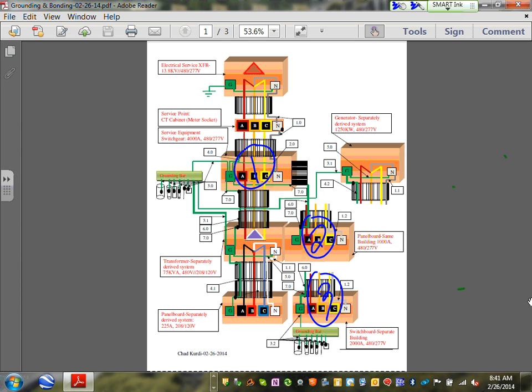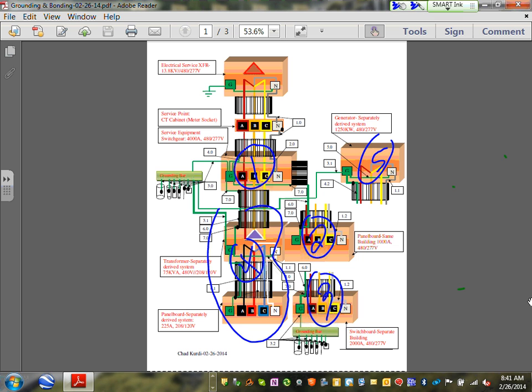And I need to do number 4. Number 4, guys, is grounding and bonding at a transformer. Number 4, which is grounding and bonding at a transformer that feeds a panel that we own and operate. That's called a separately derived system. And number 5 is grounding and bonding at a generator, separately derived system or non-separately derived system generator. So I'm going to go over 4 and 5. Any comments, gentlemen? Any questions? So let's go to, I'm going to start with number 4, Adam.